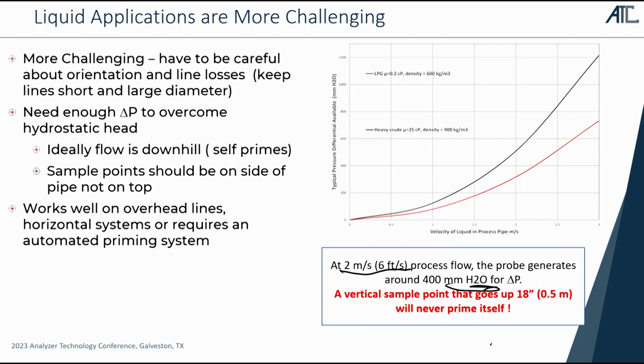If you talk to people who put scoop probes or flow impact probes on liquids applications, they'll say, we tried it and it didn't work. And it doesn't work if you don't install it properly. If you put that probe in vertically on the top of the pipe, the differential pressure has to overcome the hydrostatic head. If the line runs up towards the analyzer, it will never prime. To do these installations, we have to make sure the probe is installed on the side of the pipe, and ideally the analyzer is lower than it, so we have a downhill run for liquids that will self-prime. Otherwise, we've got to put a mechanism for priming in.